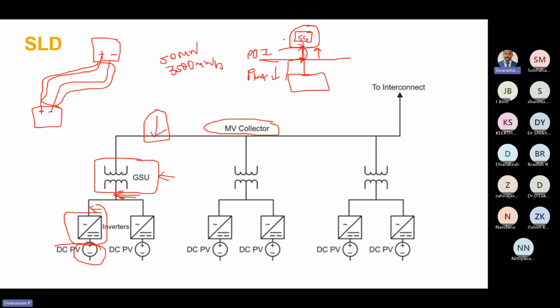Here the difference is that if we consider this location, we need not consider the losses in the transmission line. So in the AC losses, the transmission line losses will be excluded if we consider the compliance point at the plant level. Suppose we need to comply at the interconnection location. This point is called the point of interconnection, POI. This point is the point of connection, POC. So if we consider the POI, then we have to include the losses in the transmission line as well, in the AC loss.